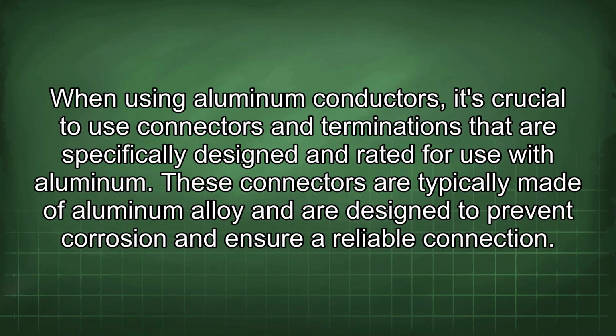When using aluminum conductors, it's crucial to use connectors and terminations that are specifically designed and rated for use with aluminum. These connectors are typically made of aluminum alloy and are designed to prevent corrosion and ensure a reliable connection.